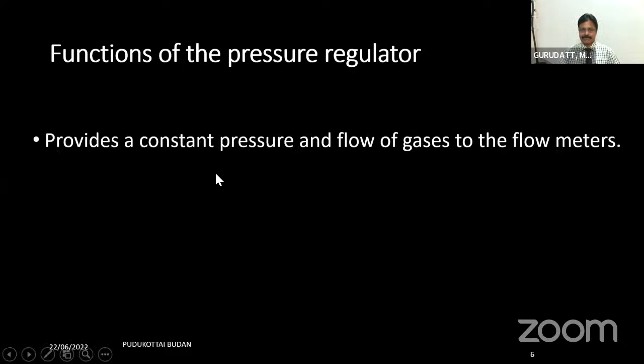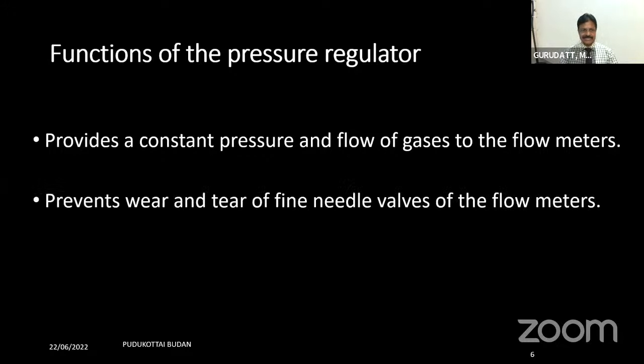So in order to prevent that, the most important function of the pressure regulator is to provide a constant pressure and flow of gases to the flow meters. Suppose I introduce a pressure regulator between the cylinder and the flow meters. The cylinder pressure is now reduced to 45 psig. Till the pressure in the system is reduced to 45 psig and below, the flow, whatever I've set in the flow meters, will not alter. So this is the most important function of the pressure regulator, why a pressure regulator has to be there.